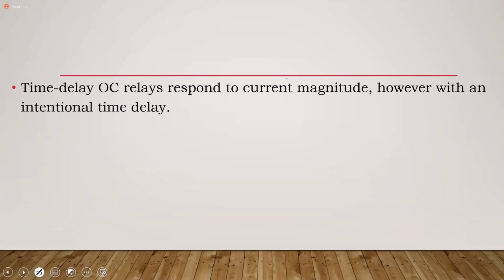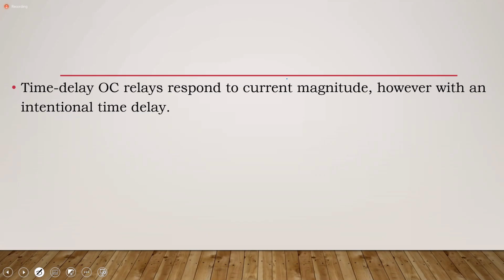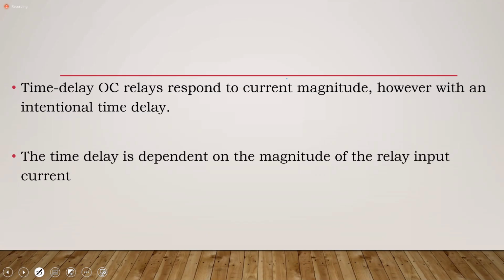So coming back to what was asked earlier, the time delay overcurrent relay responds to the current magnitude, but there is an intentional delay. So there are overcurrent relays where, once they reach a threshold current to trip, a specified amount of time is built in to say, wait and then trip. So you wait 10 milliseconds, then trip. Sir, if the current goes back below the threshold during this time, will it reset? Yes. Okay, thank you, sir.